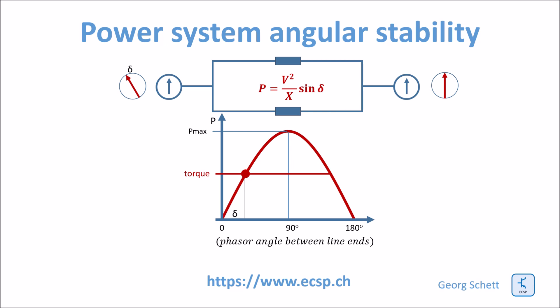And there would be a phase angle established, the rotor angle would be established accordingly. Now, for whatever reason, we would lose one of the two parallel lines. And then the curve would suddenly look as follows. So you see that based on this curve, we cannot transmit anymore the full power. So what would now happen is that this first original equilibrium we had with a certain phase angle would be reduced.